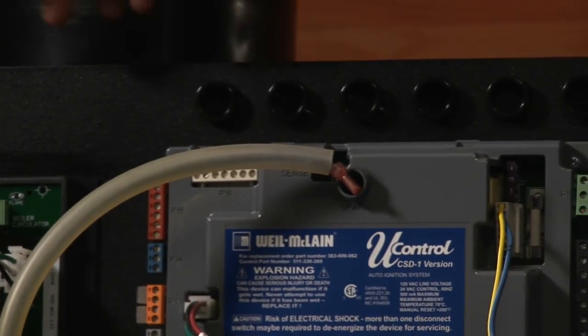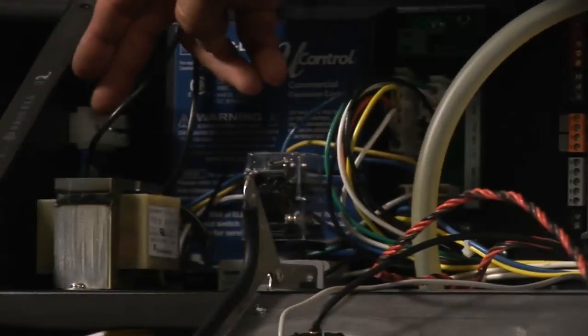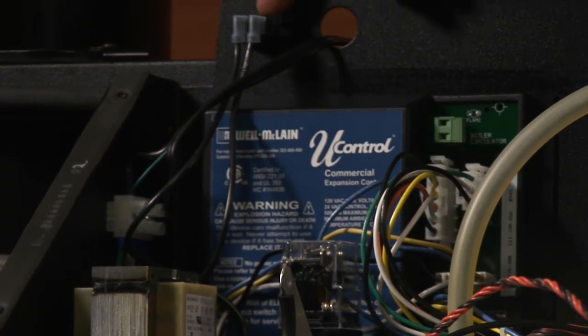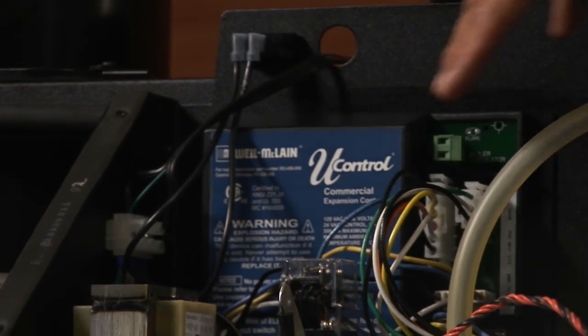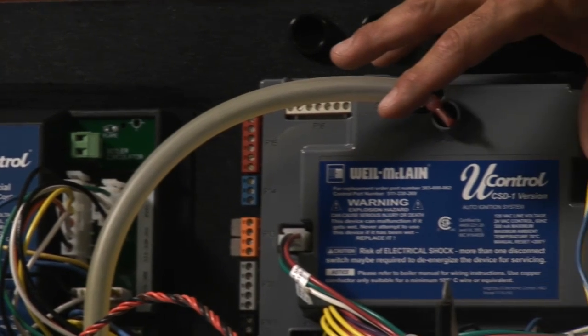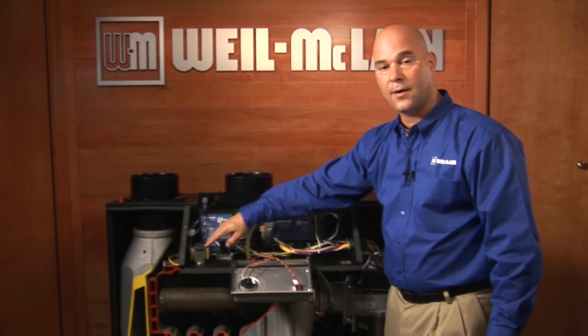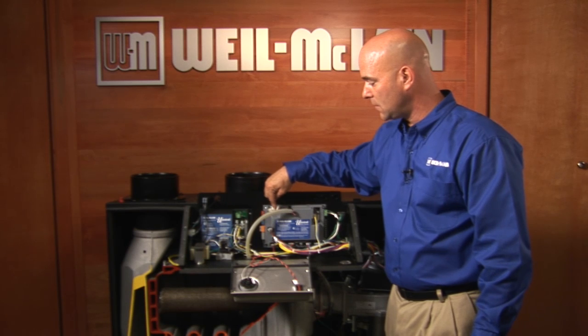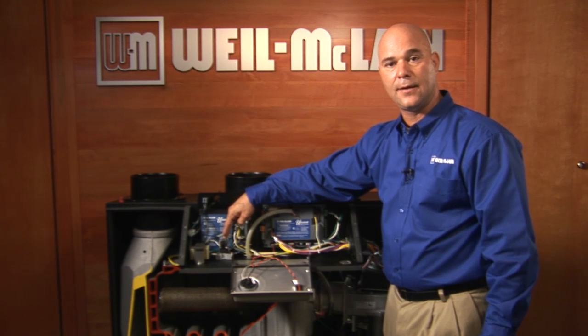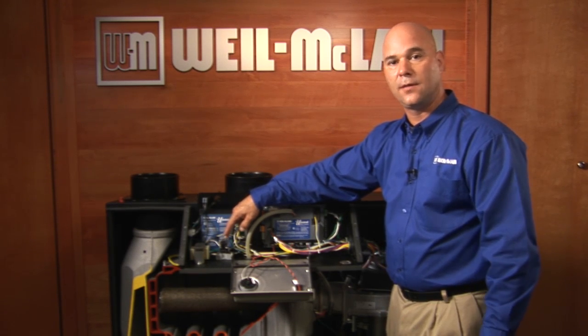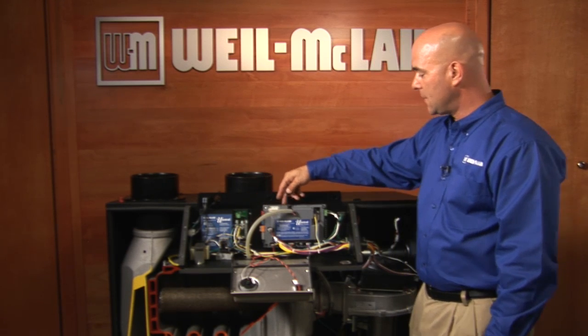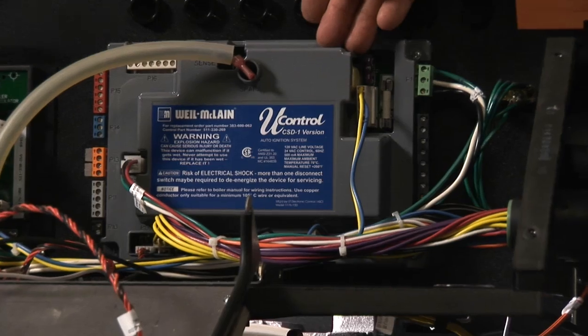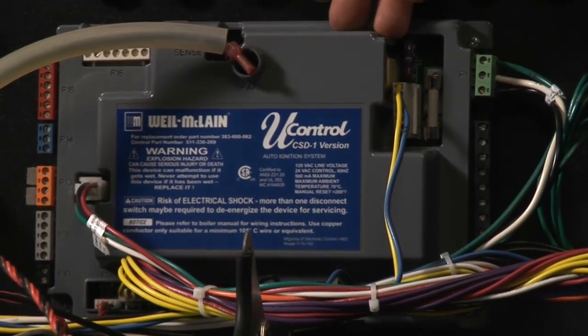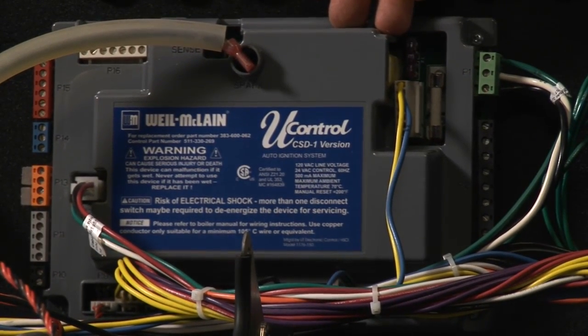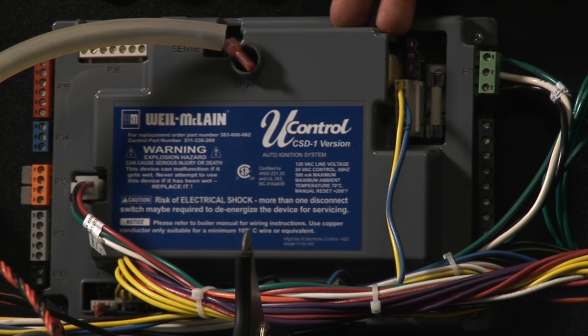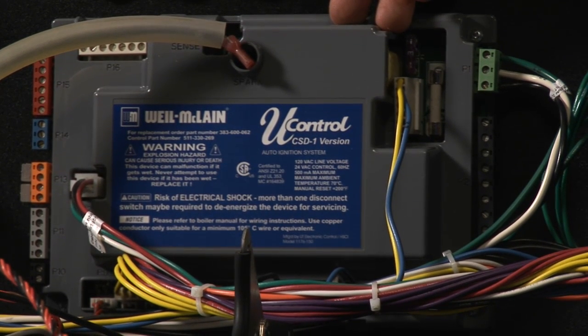The other electrical circuit is going to come in to this terminal strip, go through the switch that's on the boiler, and that will power up the U-control. There's also a transformer in here that we use in conjunction with the U-control, and then we have an isolation relay to work in conjunction with the gas valve. Coming across, this is the U-control. This meets UL 353 listing and also helps us comply with CSD1.